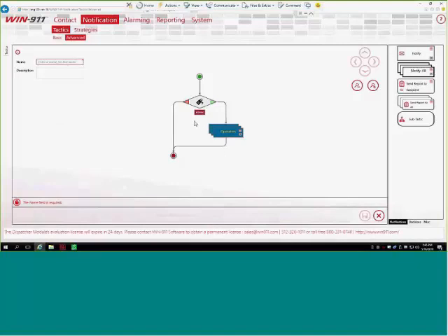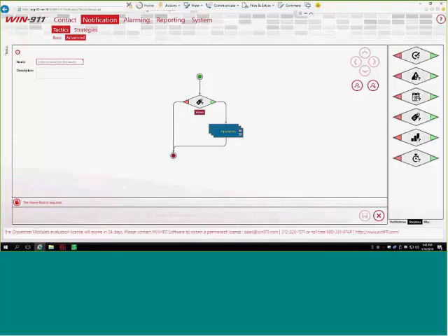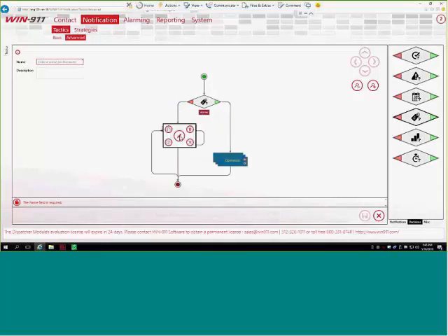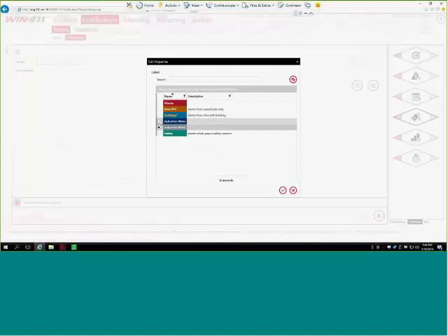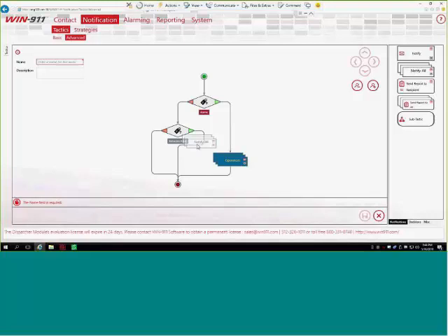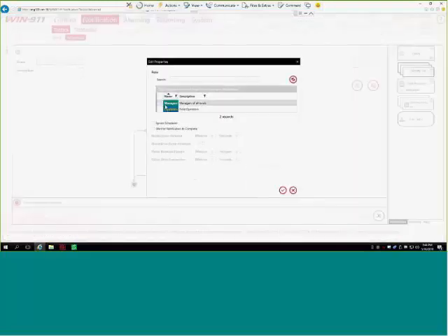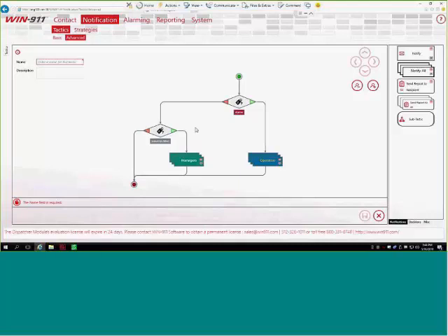Roles are a way you can group your contacts together, just like you can group your alarms together. So if it's not an alarm with the alarms label on it, then I would probably check for another one. So I can nest these. Let's say it was the wind group, then I could check for that, and then I could notify a different group of people, and so on. So I could just keep branching these down. The benefit of doing this over the basic tactic is that I'm not putting anyone's name in here, as you may notice. So that means you're creating a dynamic workflow for notification.